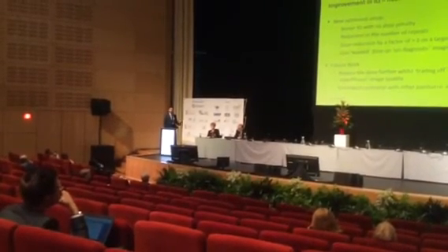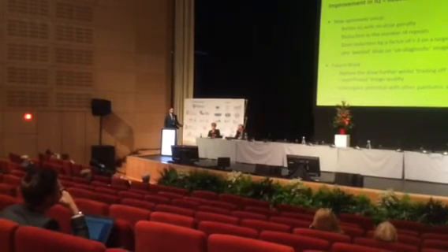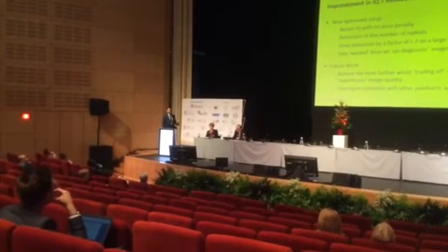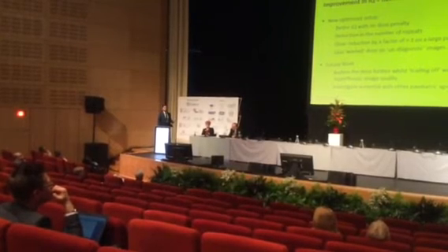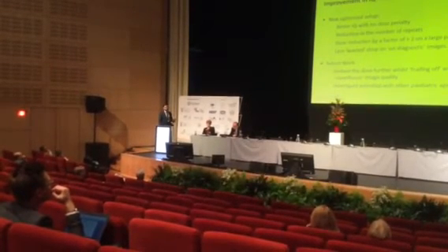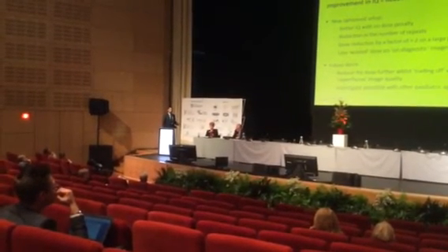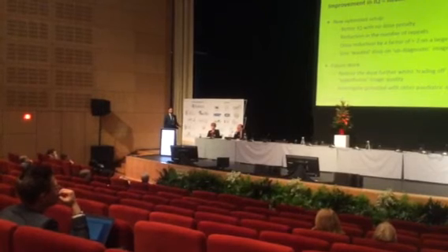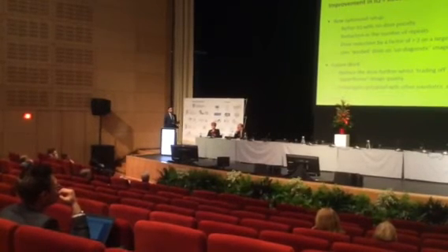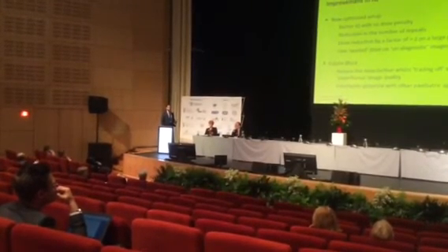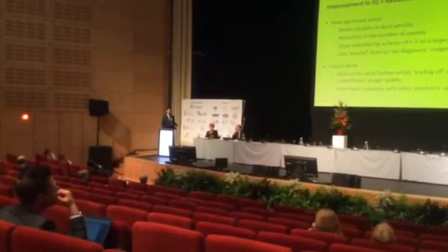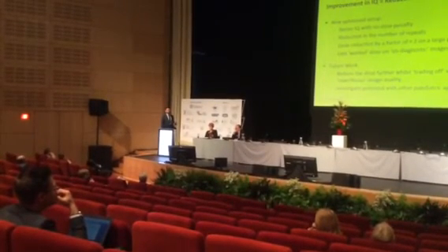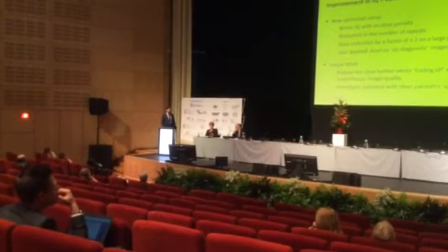So we've got significant improvement in image quality, which was the original question I was asked, but at the same time we've also had significant reduction in patient dose for a large cohort of patients. And the reason for this is that the issue we were having with repeat imaging has now been resolved. They don't need to do the repeats anymore. So therefore, a large number of these young patients are having a dose reduction by a factor of 2 or even more in some cases, and less dose is being wasted on undiagnostic images.